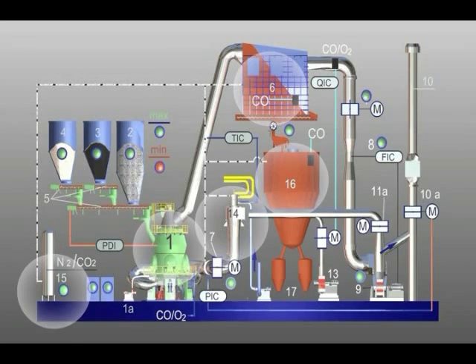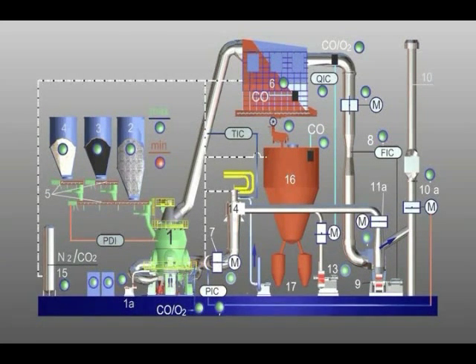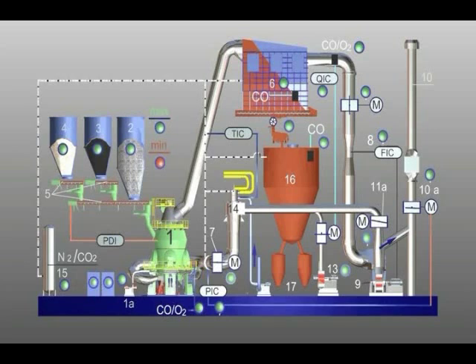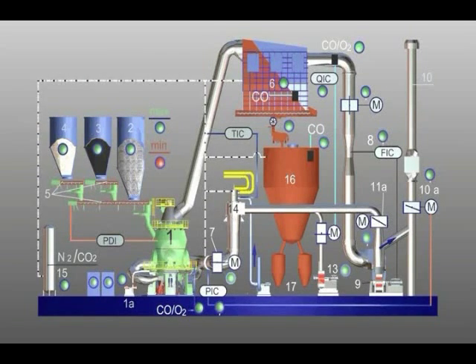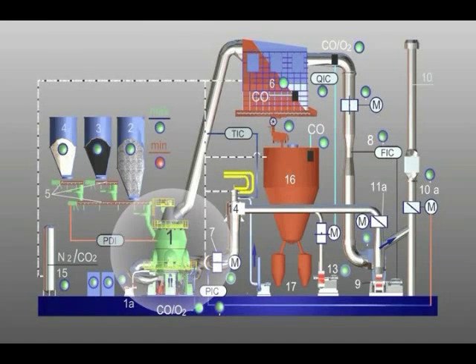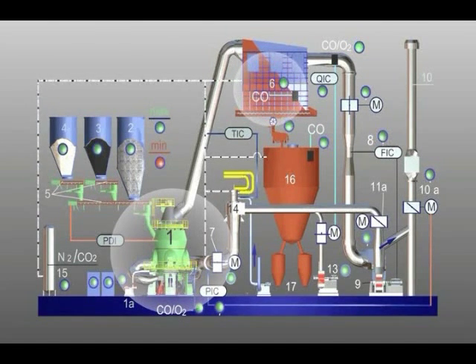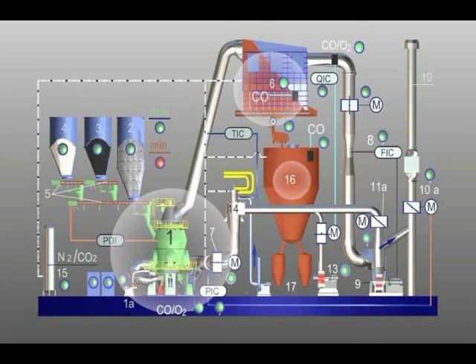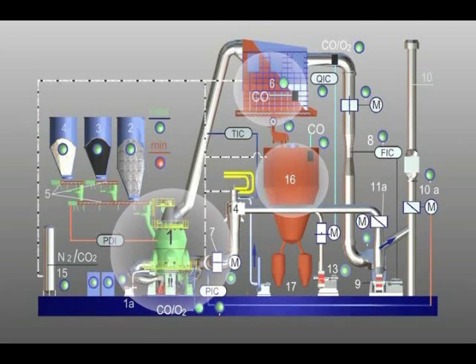The gas analysis equipment is activated in order to determine the carbon monoxide and oxygen content of the process gas. The measuring points are found at position 1, upstream of the mill, downstream of the filter, position 6. Position 6 in the filter. And position 16 in the dust hopper.